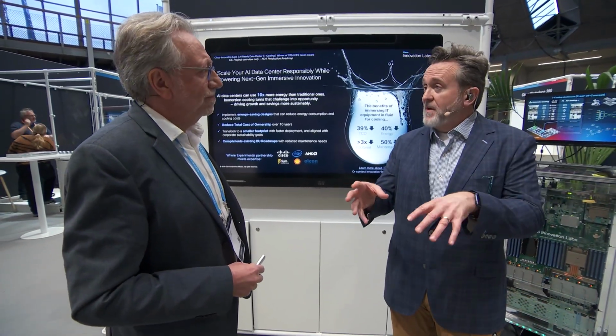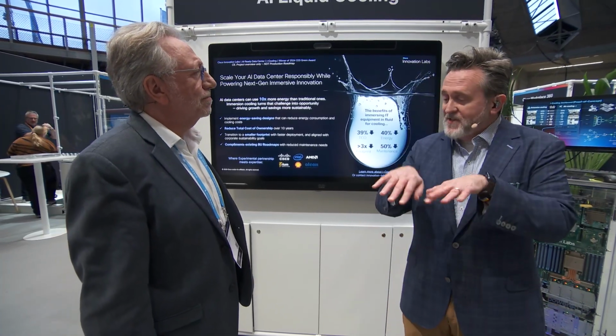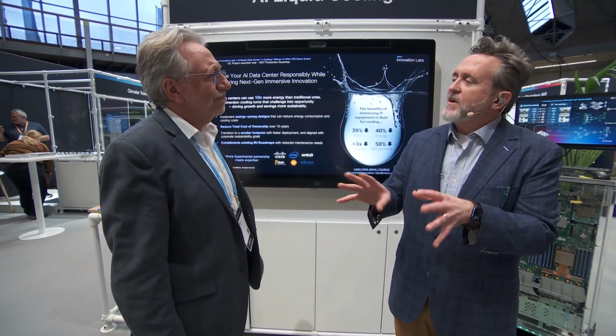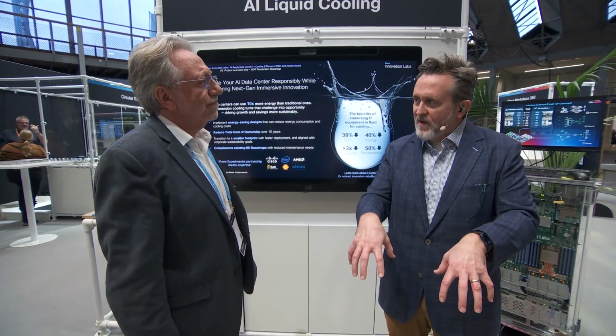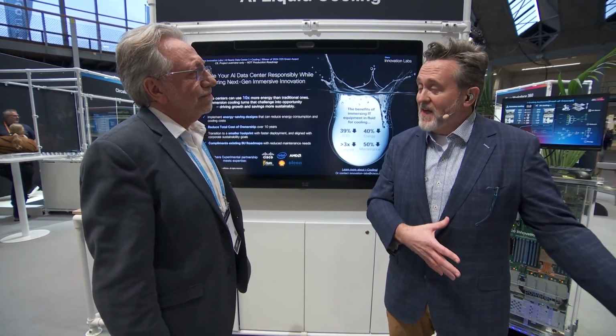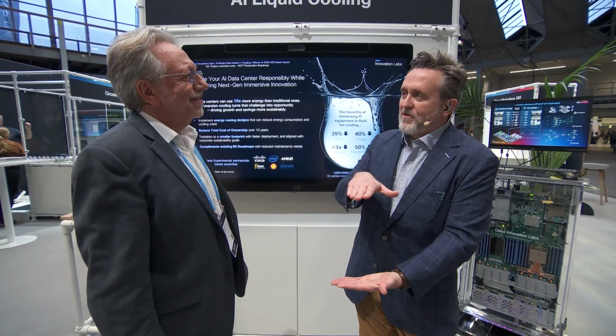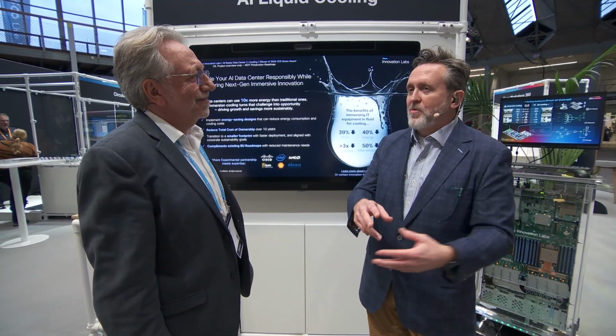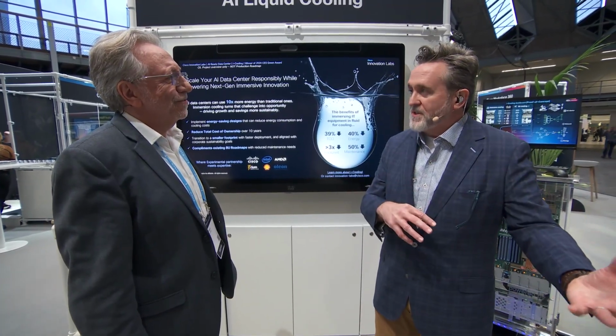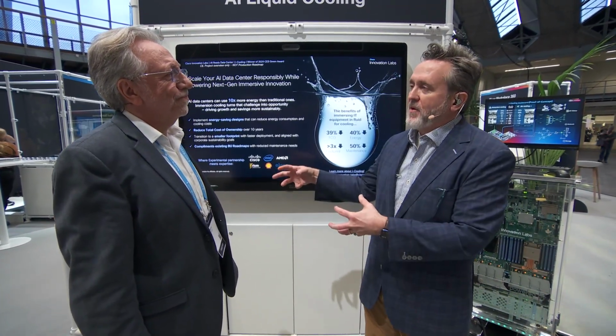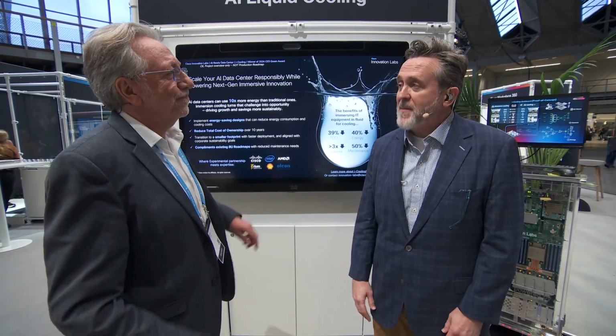This dielectric fluid you mentioned is non-conductive and safe, so it's not something we need to worry about as humans. Correct, and it can absorb more heat and get into the nooks and crannies. This not only changes the facilities we put our gear in, but also sometimes the way we design the gear. We've had examples where air cooling meant a 3RU box versus 2RU with on-chip cooling or a hybrid approach. So now you can work with stuff because of the efficiency of getting heat away from the components, which also extends their life expectancy.